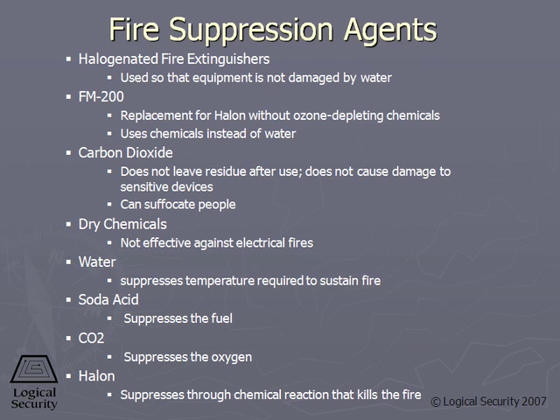Halon was a very popular fire suppressant. The problem with halon is it depletes the ozone. So the Montreal Protocol declares that halon should no longer be used as a fire suppressant. There are a whole family of halon replacements, one of them being FM200, another one is CO2. Carbon dioxide, unfortunately, has the downside of killing people. So while it effectively puts out the fire, it can be detrimental to the people in the environment.